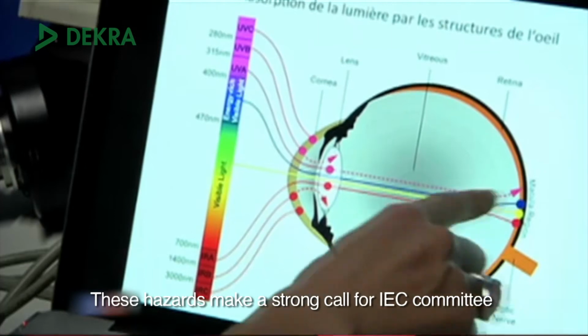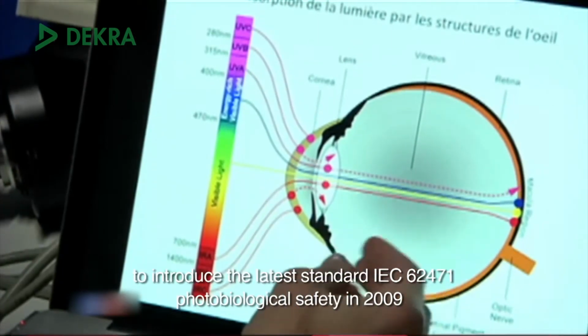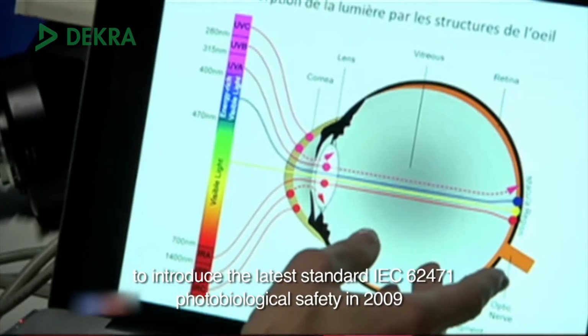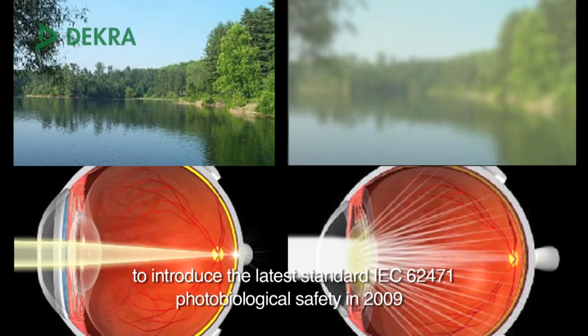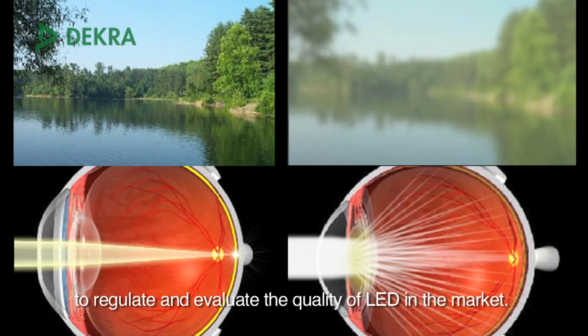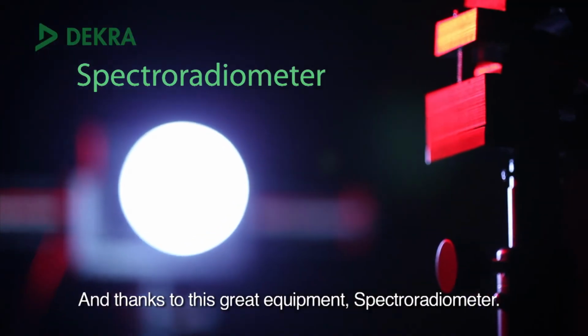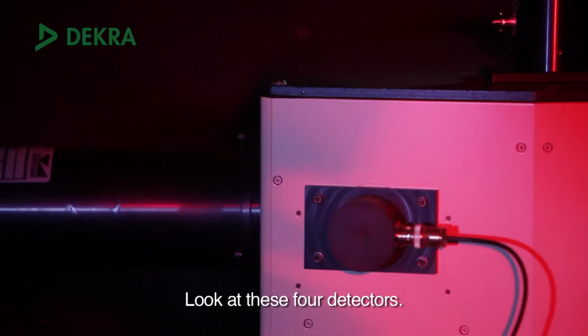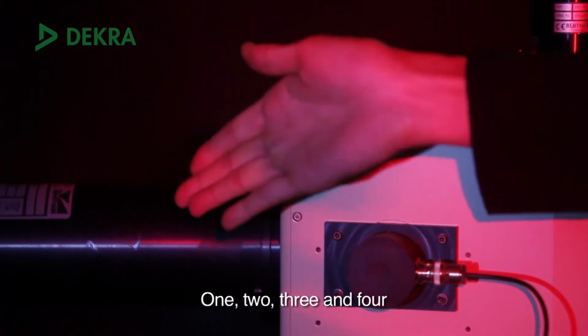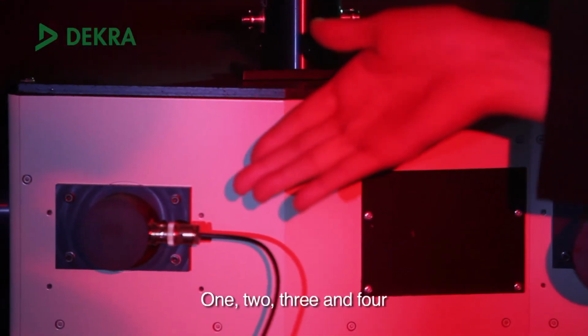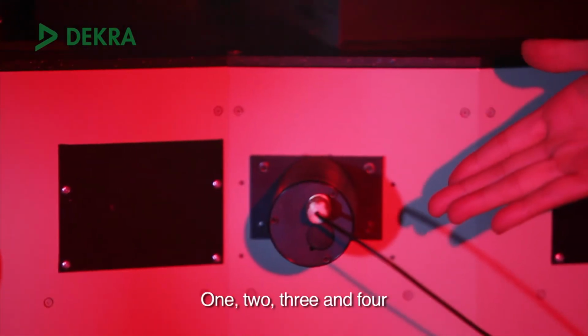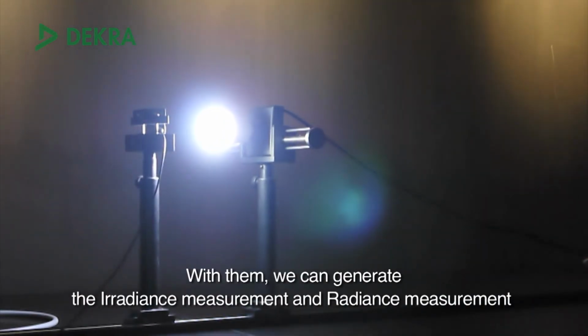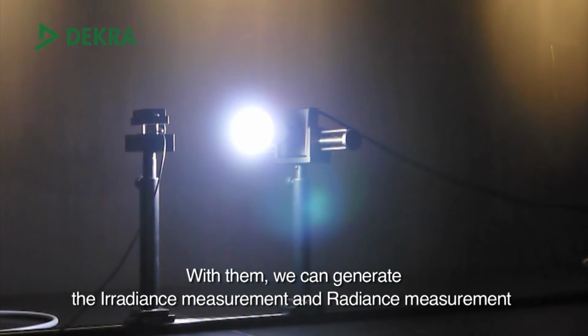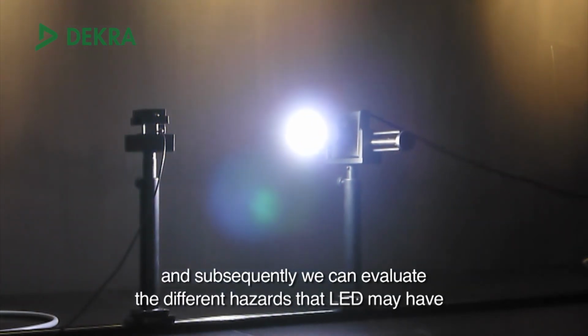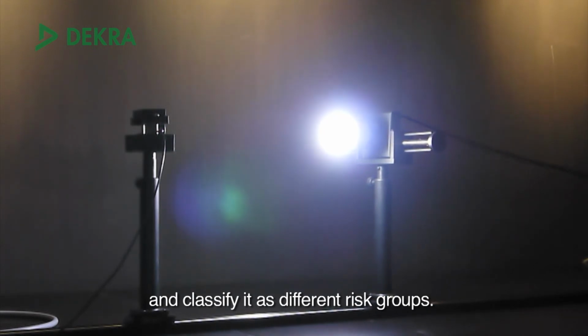These hazards make a strong call for IEC committee to introduce the latest standard IEC 62471 photobiological safety in 2009 to regulate and evaluate the quality of LED in the market. And thanks to this great equipment, spectroradiometer. Look at these 4 detectors. 1, 2, 3, and 4. With them, we can generate the irradiance measurement and radiance measurement, and subsequently we can evaluate the hazards that LED may have and classify it as different risk groups.